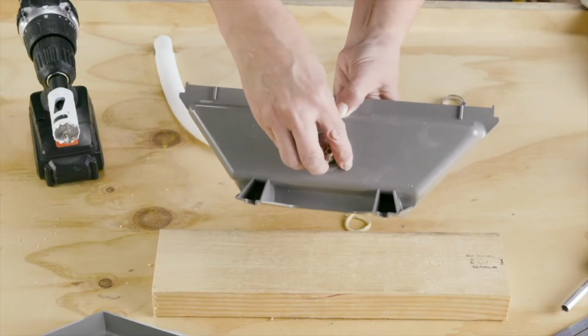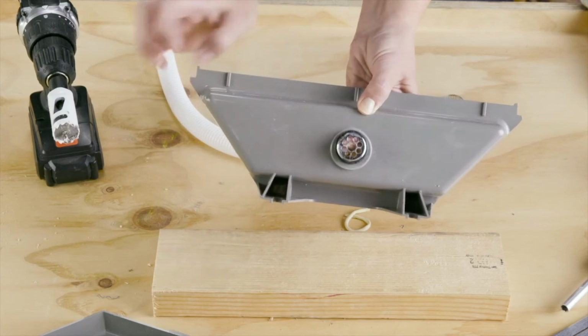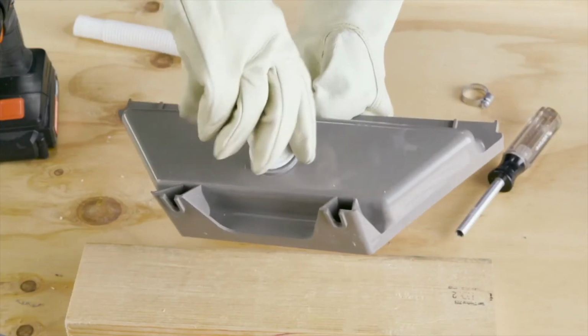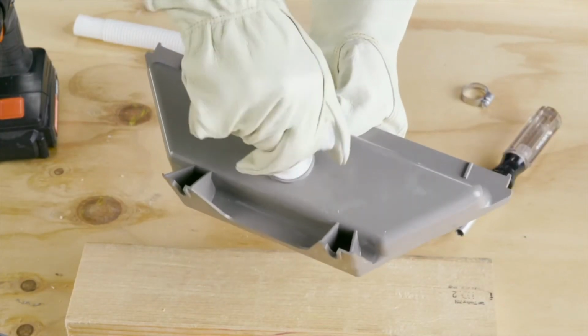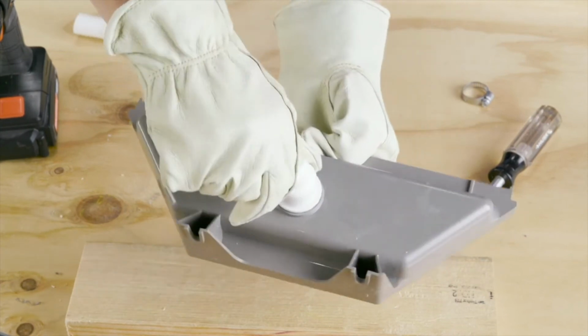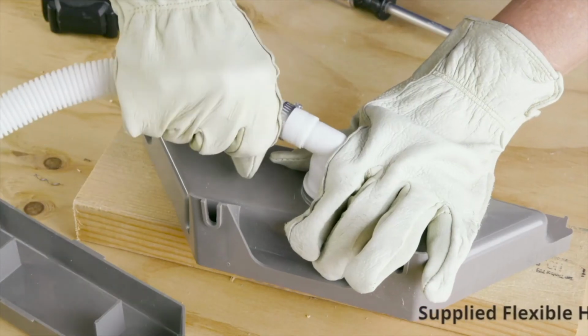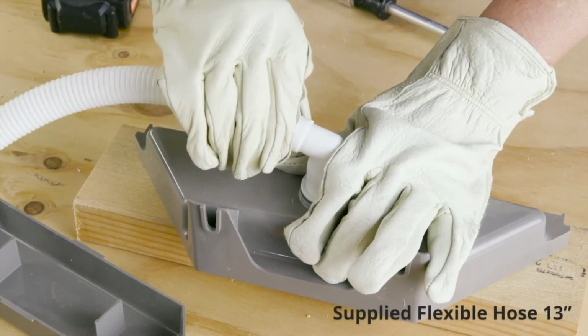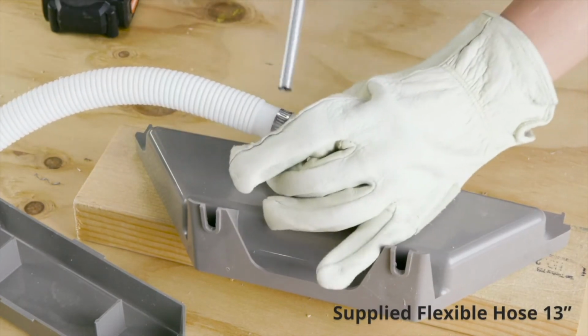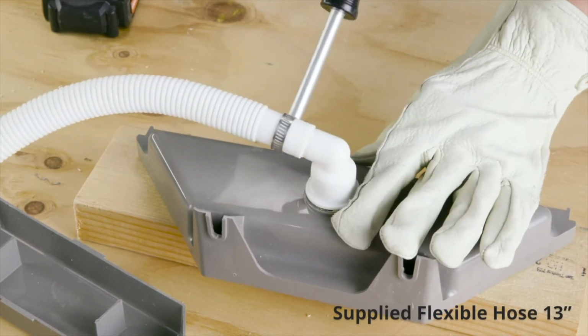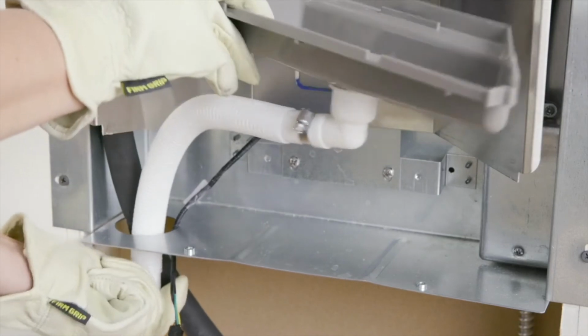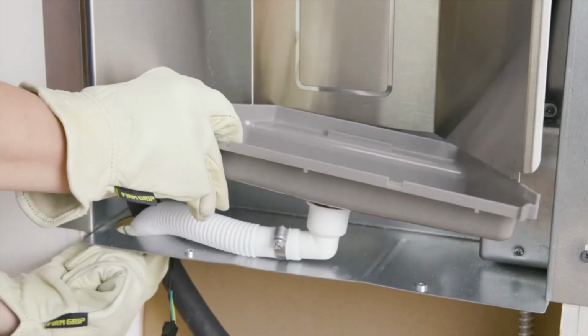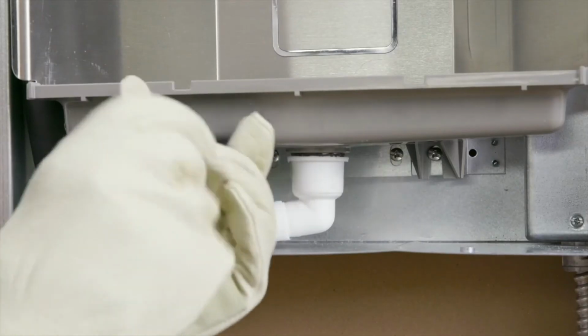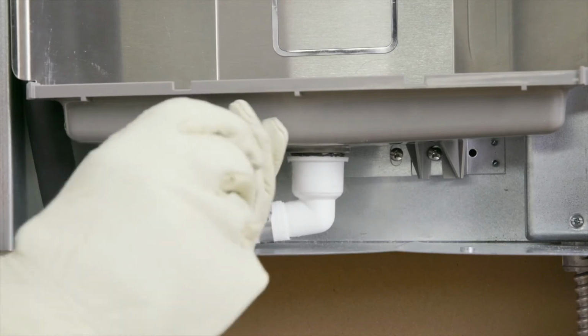Install the O-ring over the strainer threads. Put gloves back on. Thread the strainer into the drain adapter. Tighten the connection to create a watertight seal. Attach the flexible drain hose to the 3/4-inch barbed drain adapter. Tighten the clamp. Route the drain hose through the hole in the bottom left of the enclosure. Secure the drain basin back in place with the 2 screws.